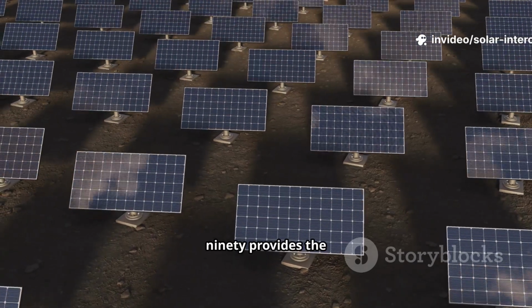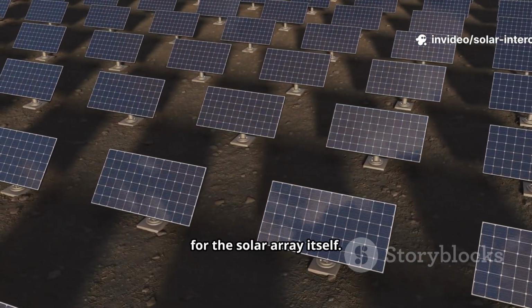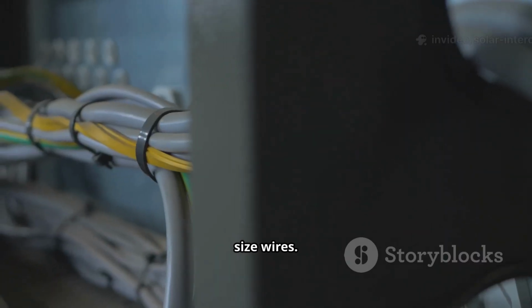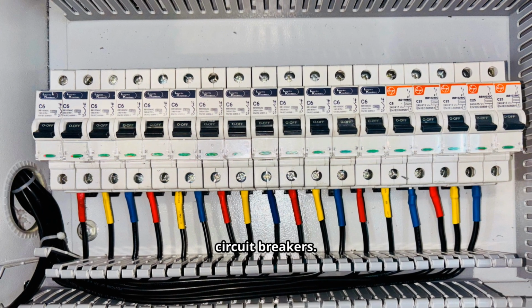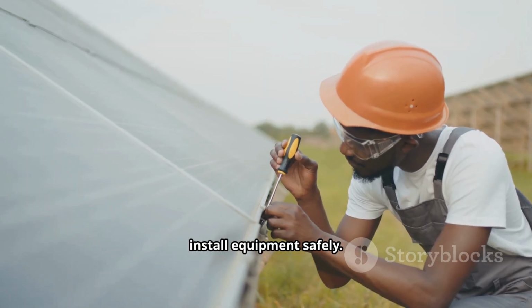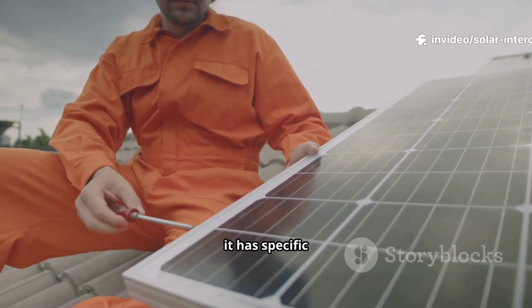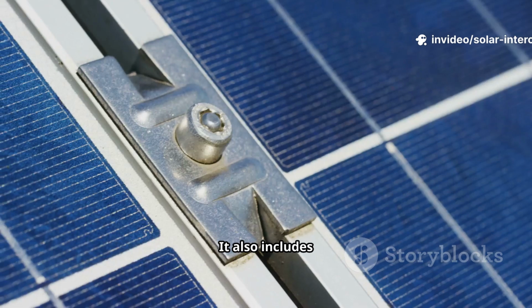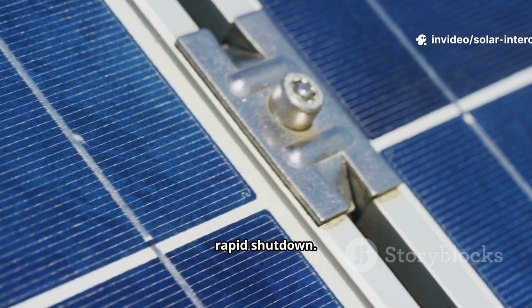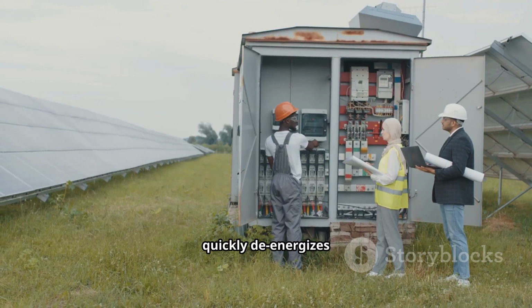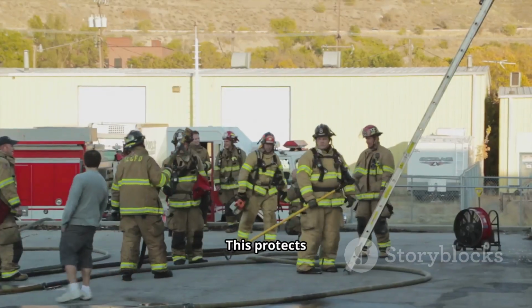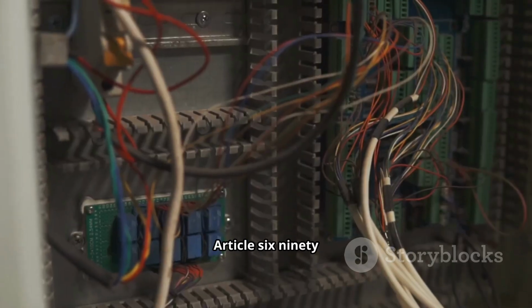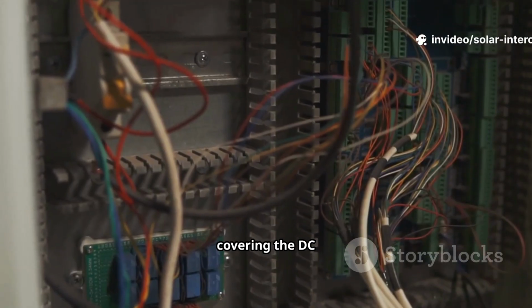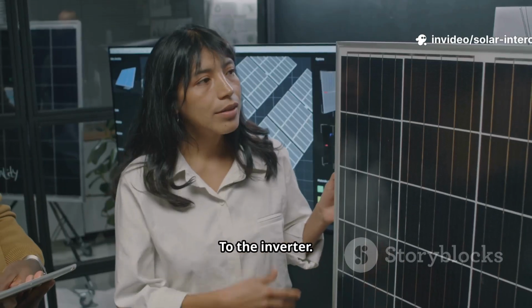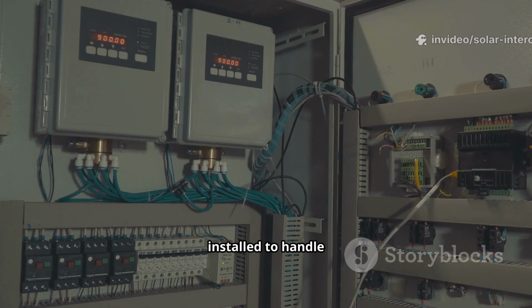NEC Article 690 provides the foundational rules for the solar array itself. It tells you how to size wires. It tells you how to select the right circuit breakers. It tells you how to install equipment safely. For example, it has specific rules for grounding the system. It also includes requirements for rapid shutdown. Rapid shutdown quickly de-energizes the solar panels on the roof. This protects firefighters in an emergency. Article 690 is comprehensive, covering the DC side of the system, from the panels to the inverter, making sure every component is installed to handle the unique characteristics of solar power.